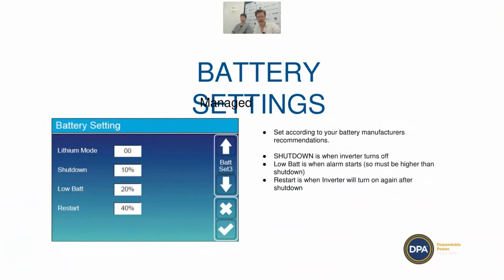This last setting is your shutdown and restart values, the same as you'd have with Victron or Selectronic. Basically, this decides at what point the inverter will stop producing any AC - it's gone past its charge from the generator or charge from the grid state of charge value, they haven't started for whatever reason, and it's getting down into emergency shutdown. So 10% is a good value, maybe slightly higher.